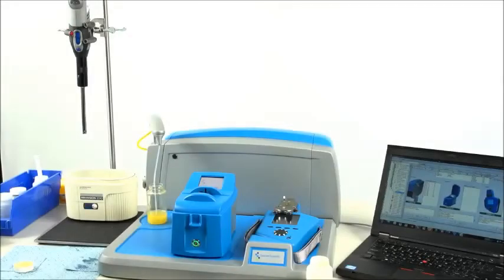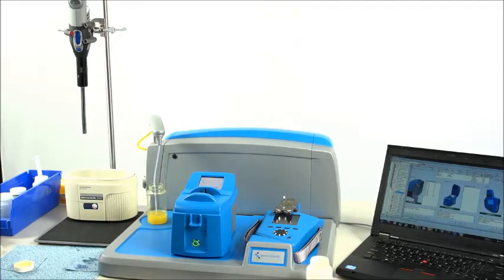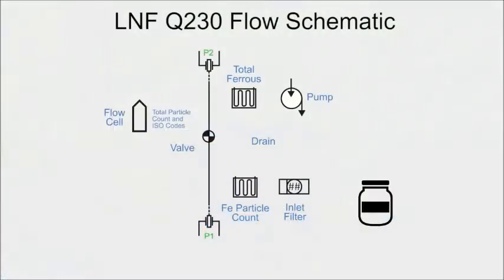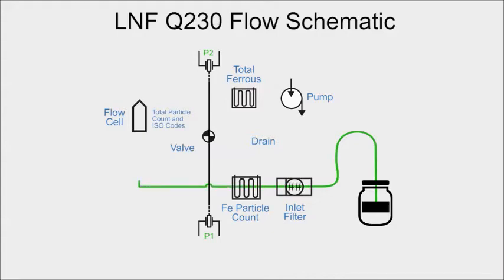After the ultrasonic, which removes the air bubbles, we process the sample on a particle counter and ferrous monitor. This test measures particle count and ferrous wear. The LNF Q230 schematic shows the flow path. The sample is drawn up through the tube, through a 100 micron filter that removes large particulates, and enters the ferrous portion—a high-sensitivity magnetometer which measures the ferrous particle count. Next, the sample enters the LNF flow cell, which uses laser light and a CCD detector to image each individual particle.